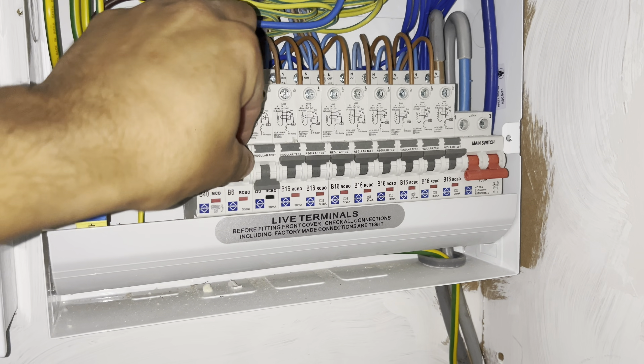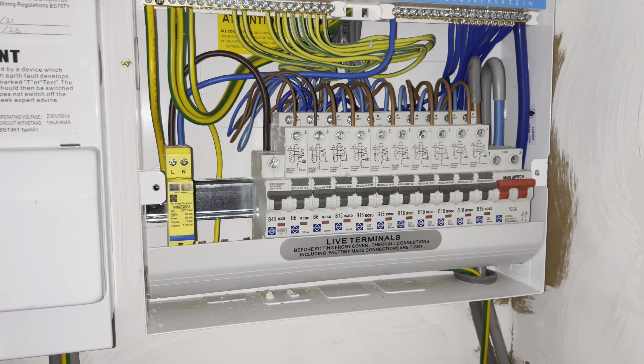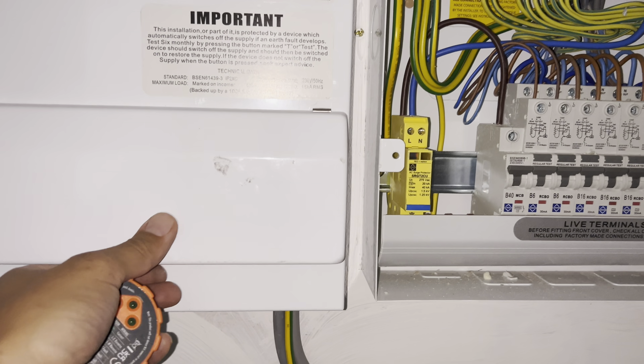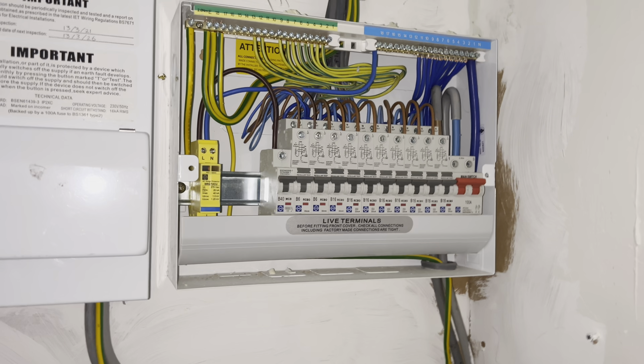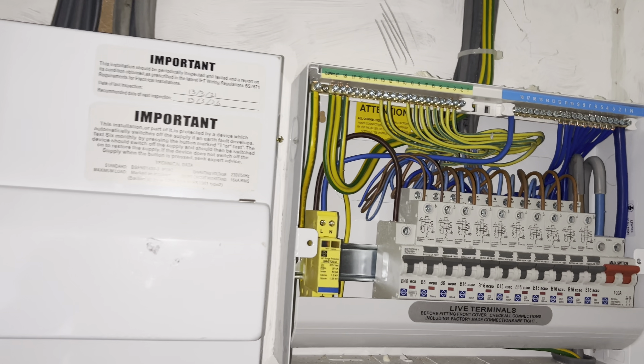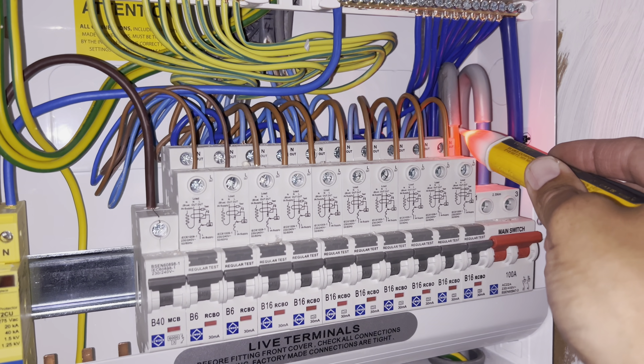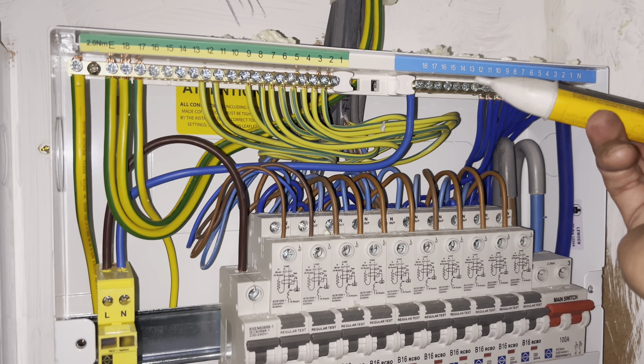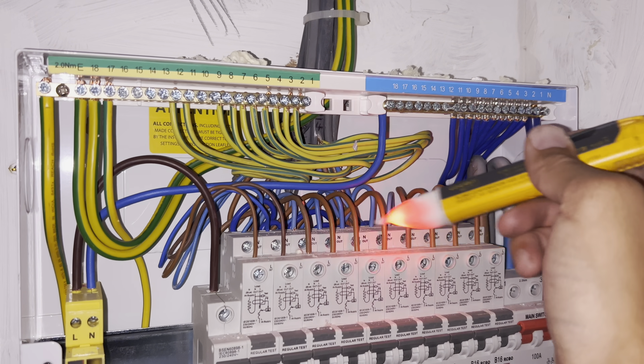So I've now swapped it around. Let's put these circuits back on — everything's connected. Main switch on for that one. Main switch on for this one. So let's have a look — the lives are live. Live here is good. The neutral here is no longer live. And that is no longer live here — it flashes anyway. No lives here as it should be, and these are all back to being live exactly as they should be.